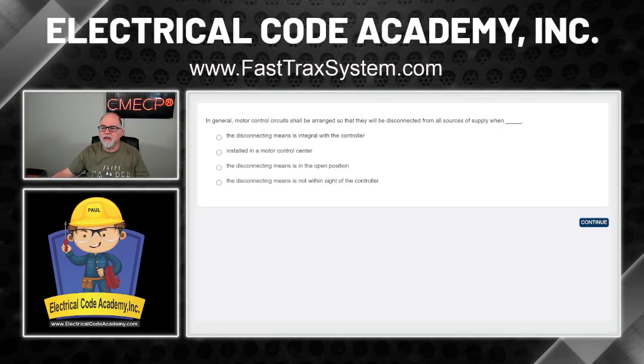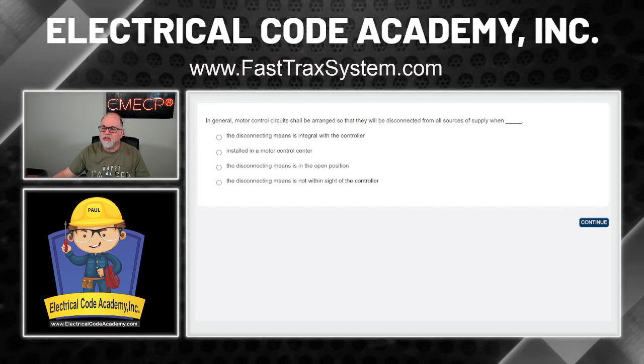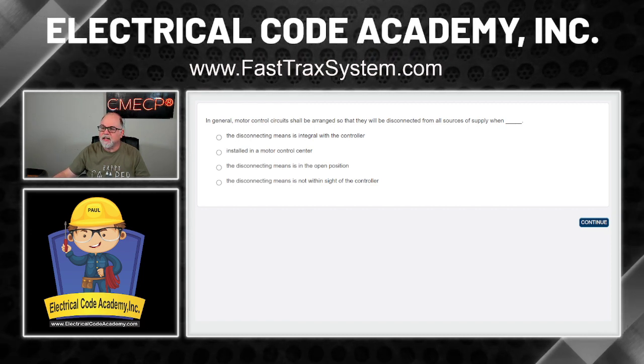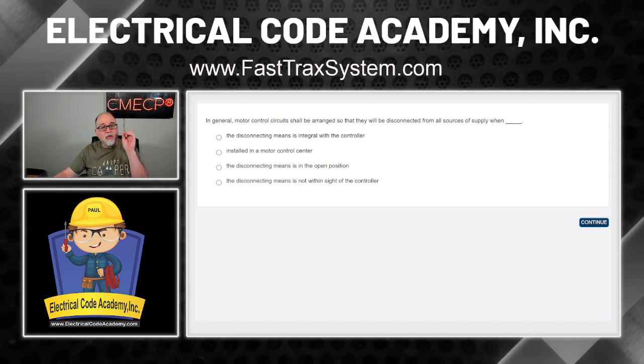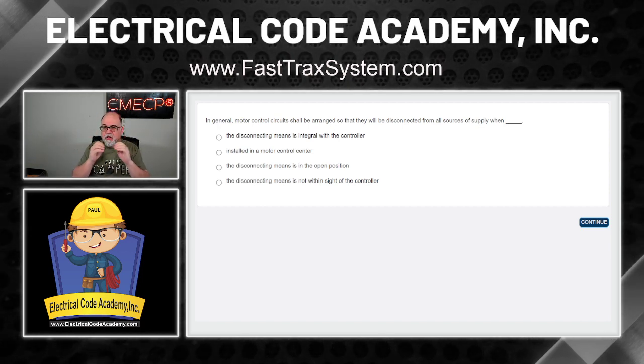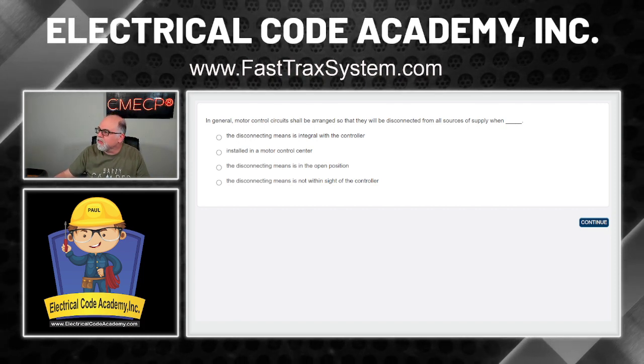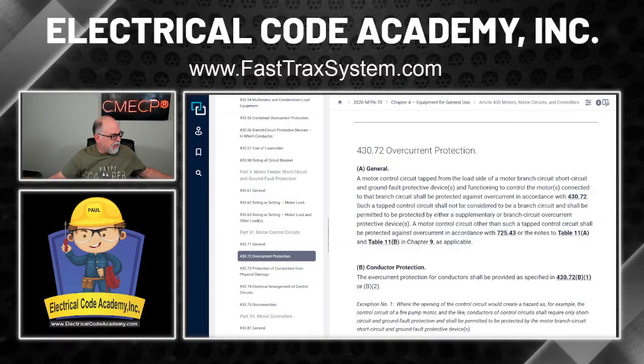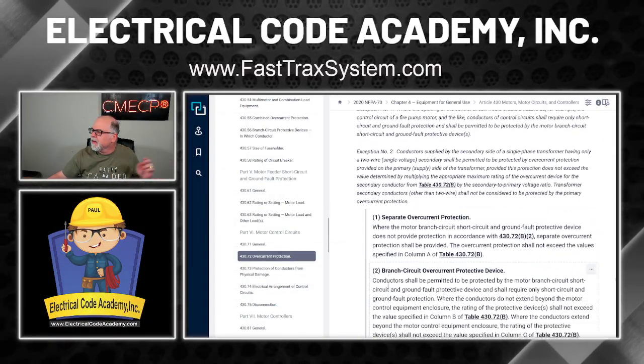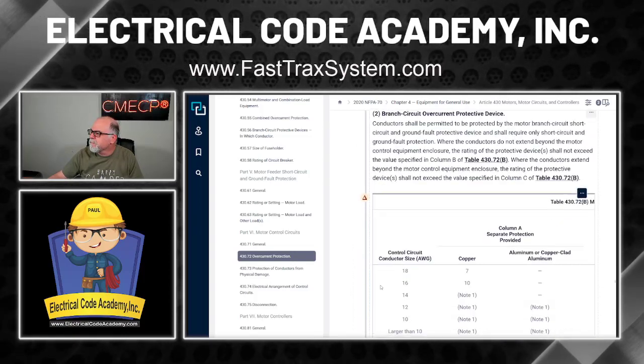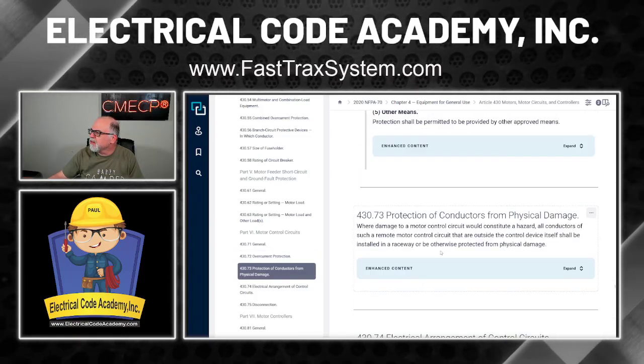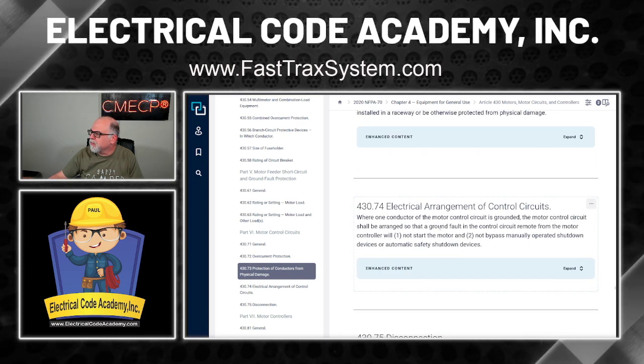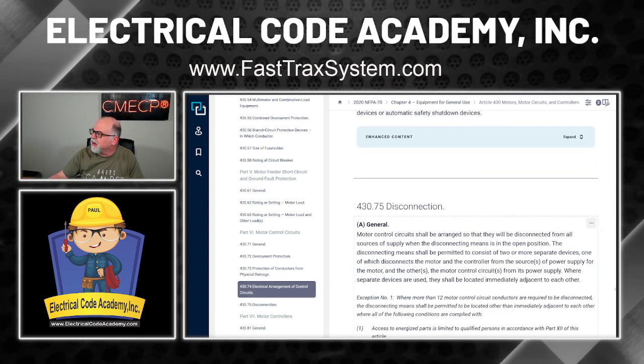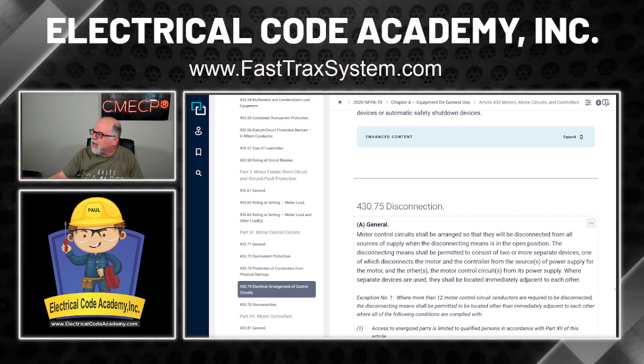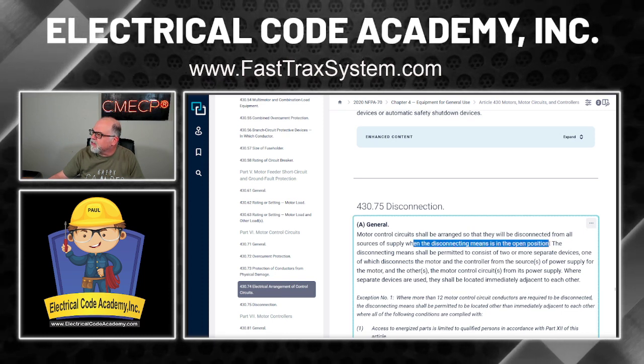All right. So back at our question, it says in general, motor control circuits shall be arranged so that they will be disconnected from all sources of supply. Okay, so that phrase, arranged so that we disconnect from all sources of supply. So let's go back over to the code real quick and see if we can figure that out. Bear with me while we go look. And we're back over here. And here's control conductors, arrangement, disconnection. Motor control circuits shall be arranged so that they will be disconnected from all sources of supply when the disconnecting means is in the open position.